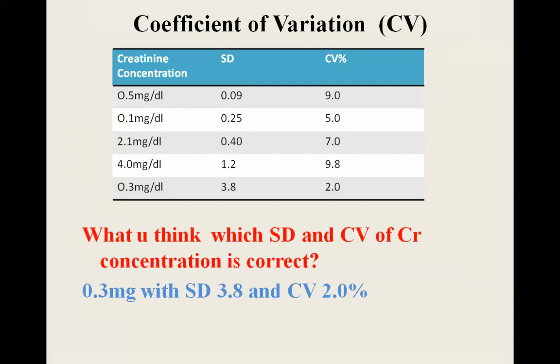Now, what is an acceptable CV, or what criteria should we use to decide the acceptable CV? There are many sources which you can use to determine the expected level of your precision. Basically, the CV is the indicator of your precision. So you can use your manufacturer's product insert, your instrument manual, your inter-laboratory comparison programs, or CLIA limits.